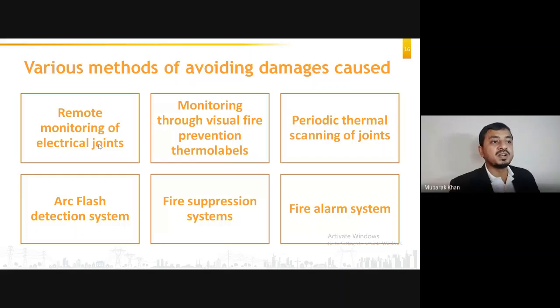Then there is one more method known as thermal imaging, periodic thermal scanning of joints, where you take images of these joints over a period of time, like every 3 months, 6 months, or maybe monthly. Some people are doing this. You take a picture of the joint, and if some joint is getting overheated, you take a corrective action on that. Then there is an arc flash detection system, right? When the arc flash occurs, it tries to switch off the panel as fast as possible. People are also using fire suppression systems, so that if there is a fire in the panel, it will extinguish it in the shortest possible time. Then we have a fire alarm system. Definitely, if smoke comes out of the panel, then the fire alarm system will act. So these are the various methods. We will try to see what is the comparison between them.